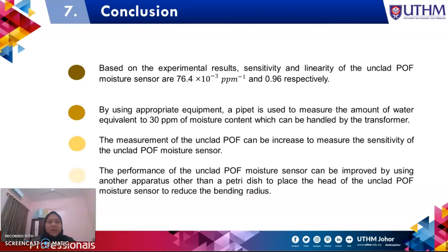For future work, we suggest using appropriate equipment, such as a pipette, to measure the amount of water equivalent to 30 ppm of moisture content in the transformer oil. The second suggestion is that the length of the unclad POF can be increased to more than 1 cm to measure the sensitivity of the unclad POF moisture sensor. And the last one is that the performance of the unclad POF moisture sensor can be improved by using another apparatus other than a petri dish to place the head of the sensor, to reduce the bending radius.